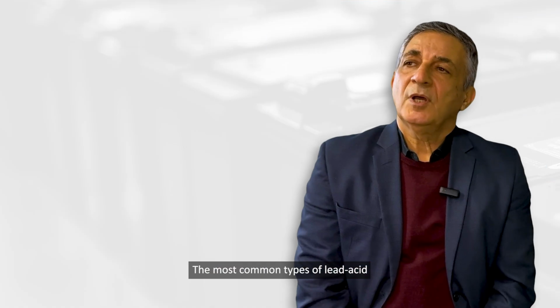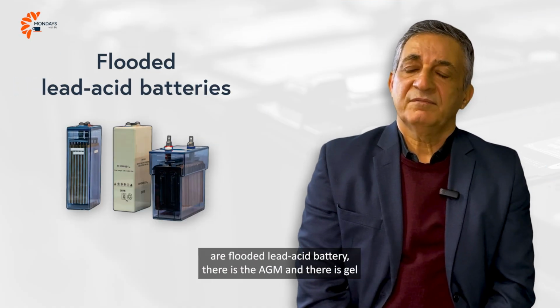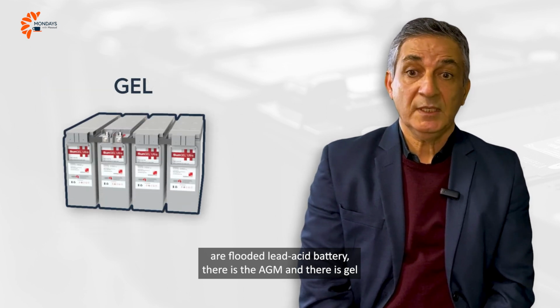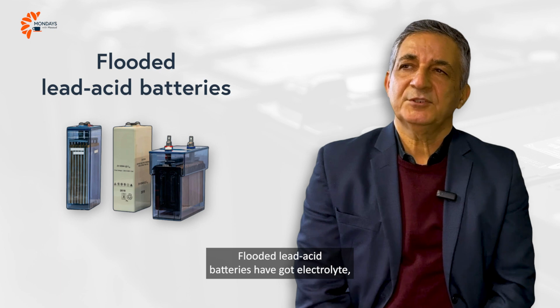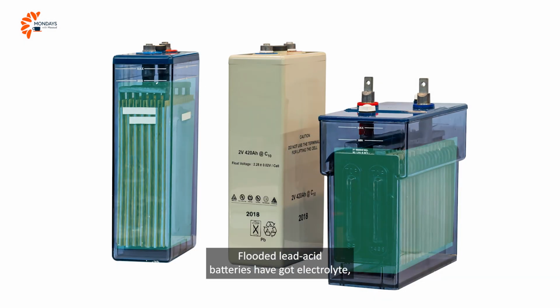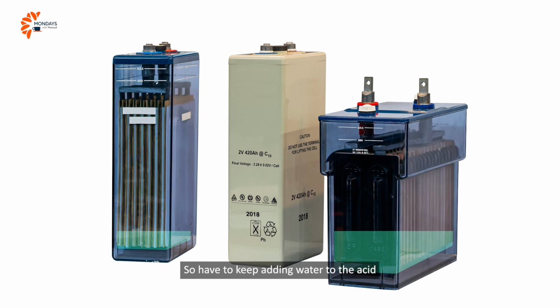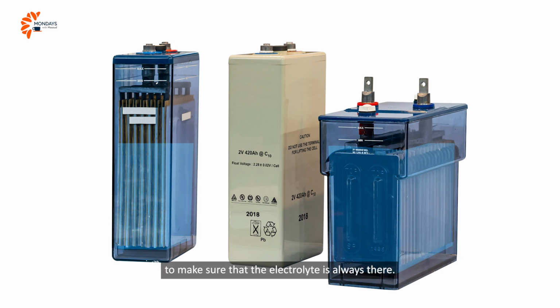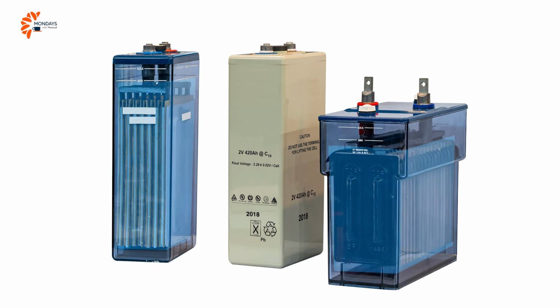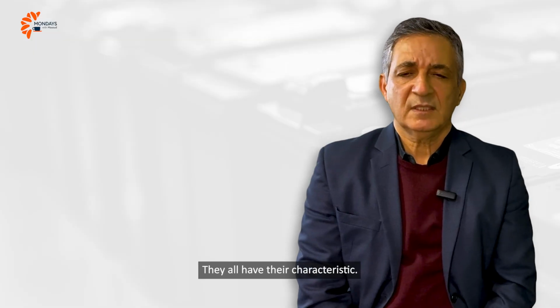The most common types of lead acid are a flooded lead acid battery, there is the AGM, and there is gel. Flooded lead acid batteries have got electrolyte, which is acid, and you can see it. That electrolyte also evaporates, so you have to keep adding water to the acid to make sure that the electrolyte is always there. They all have their characteristics.